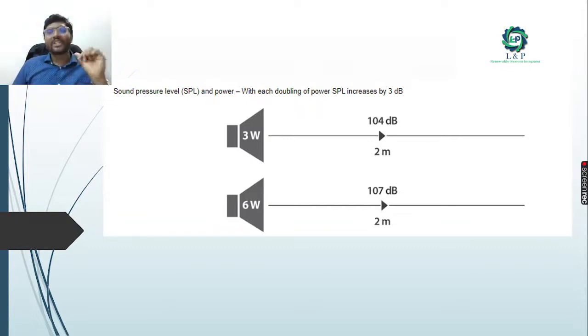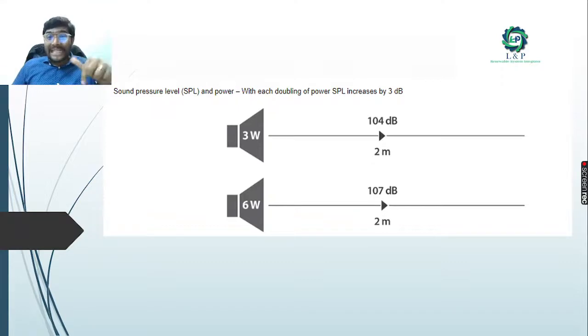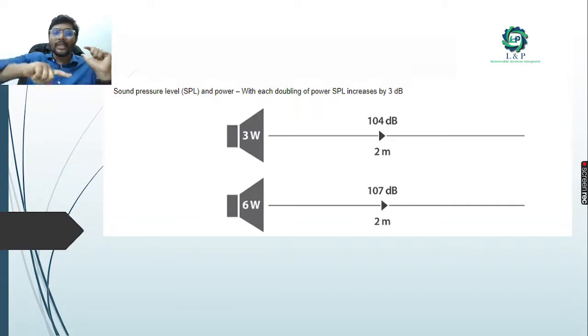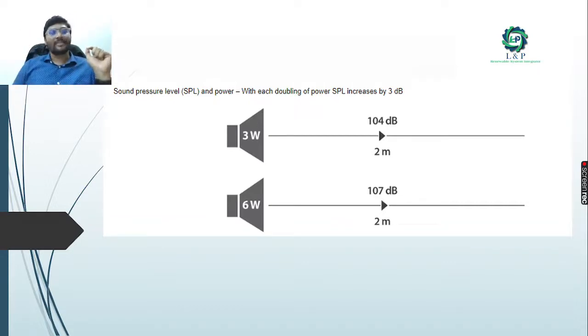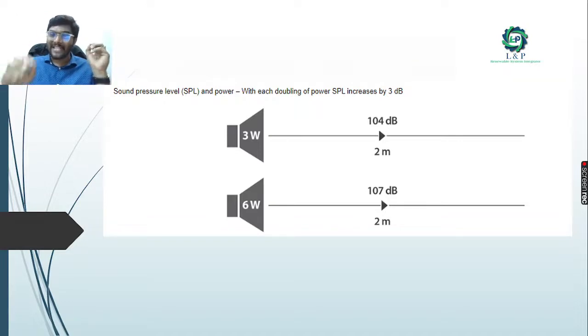Now relating SPL to power: a 3-watt speaker producing 104 dB at 2 meters - if we double the power, the SPL increases by 3 dB. So at 3 watts it produces 104 dB, and when we double the power to 6 watts, it produces 107 dB at 2 meters. This is an important calculation when designing speaker placement inside a building.